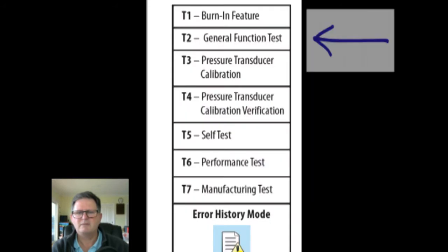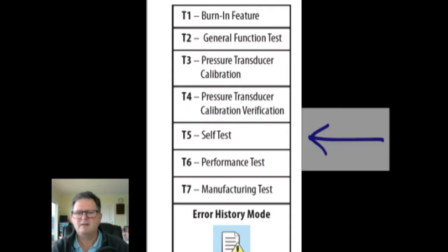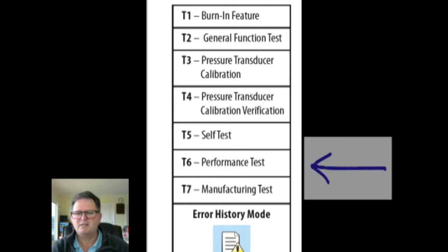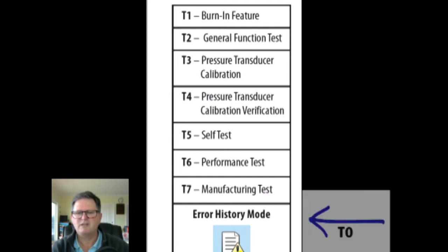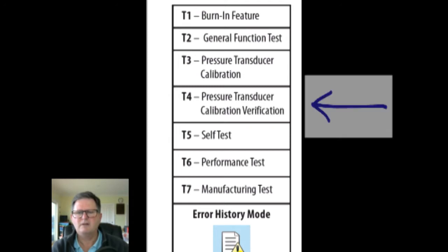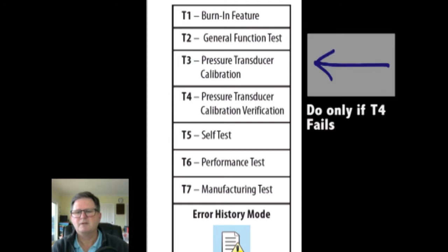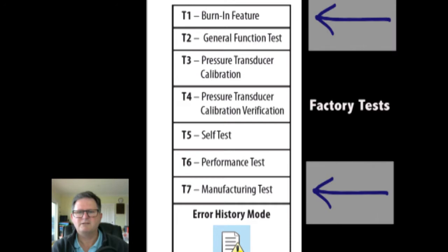So this is covering the test modes we're going to look at today. Performance test, self-test, general function test, T0, which is the error history, and verification of pressures. There's no need to do T3 unless T4 fails, and it rarely does, and the other two tests are just factory tests we won't be doing.